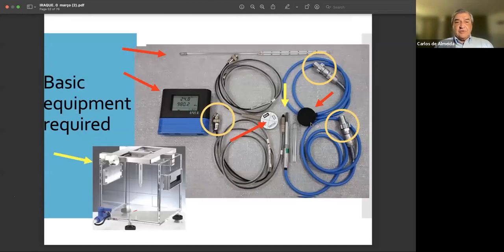Now, the basic instruments that we need in the hospital are a water phantom and a good barometer. This is probably one of the most common mistakes that medical physicists make when they take measurements at high altitudes: one mistake is to call the airport and ask what the pressure is there. If the airport is at the same altitude as you, it's probably okay, but if it's not, you may be making mistakes.